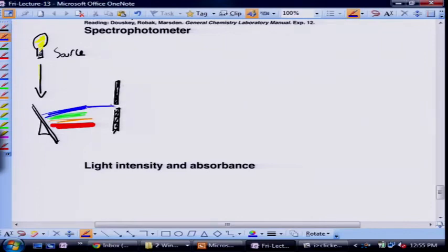Okay, so imagine, it doesn't look very lined up there. These are guard slits. And guard slits are there to take a fat band of light that may be, say, 40 nanometers, and then you can basically close down these guard slits and block the edges, so you're just taking, like, say, 1 or 2 nanometers of that color. Okay? So it gives you finer control. This narrows the band.